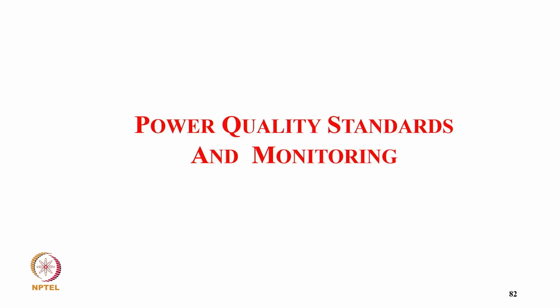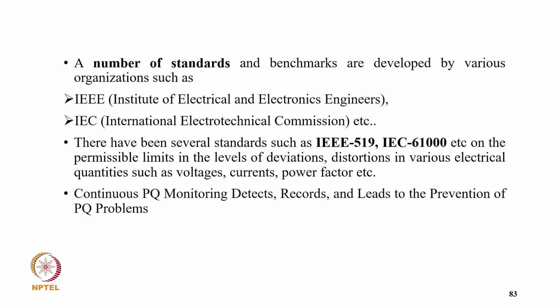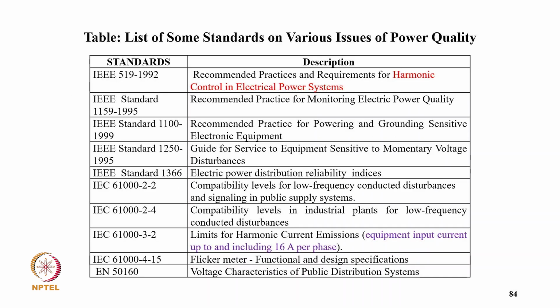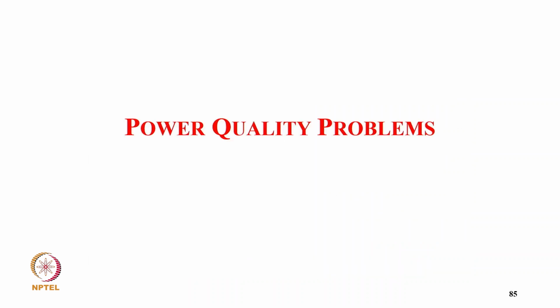Now coming to power quality standards and monitoring. A number of standards and benchmarks are developed by various organizations such as IEEE and IEC. They have several standards like IEEE 519 and IEC 61000 on permissible limits and the level of deviation and distortion in various electrical quantities such as voltage, current, and power factor. Continuous power quality monitoring detects, records, and leads to the prevention of power quality problems. And this is the list of some of the standards for various issues of power quality problems.